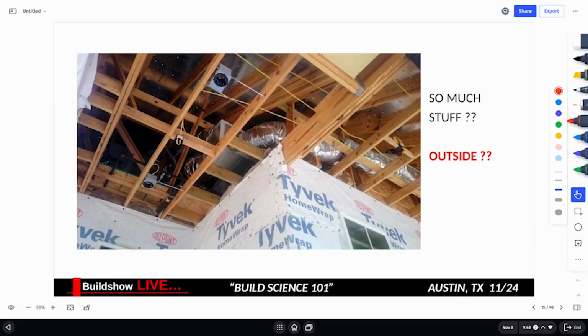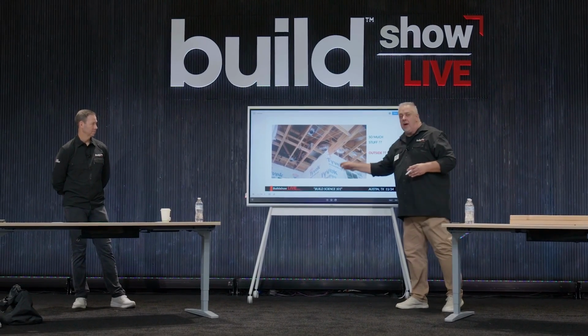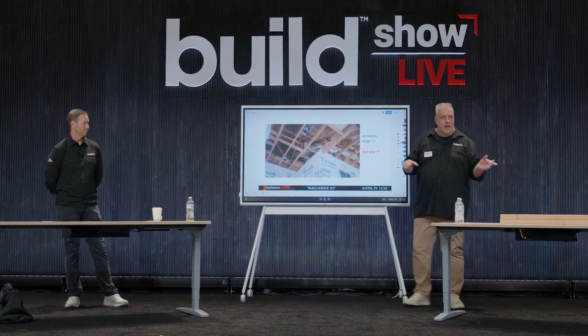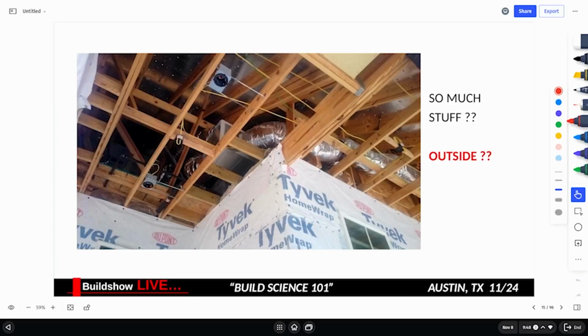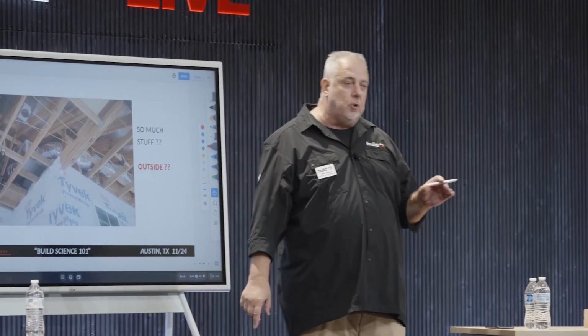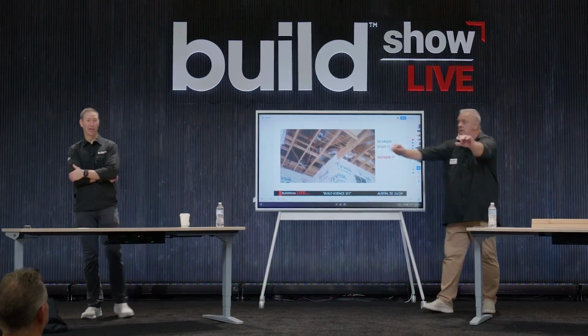Rather than make the house 200 square feet bigger and put a mechanical room in the house, he ran the ductwork on the outside. So think about it for a second, right? We cool that air, we run it down a duct at what, 60 degrees, expecting our house to be at 70 degrees, but we immediately run that duct through a 165 degree attic. That's ludicrous, right? I don't know if you've ever heard Joe speak, but one of his favorite lines is, "Don't do stupid things." It's really stupid, Steve. And unfortunately, incredibly common.